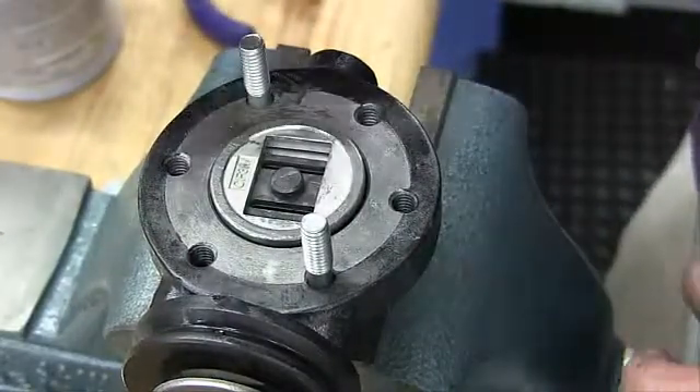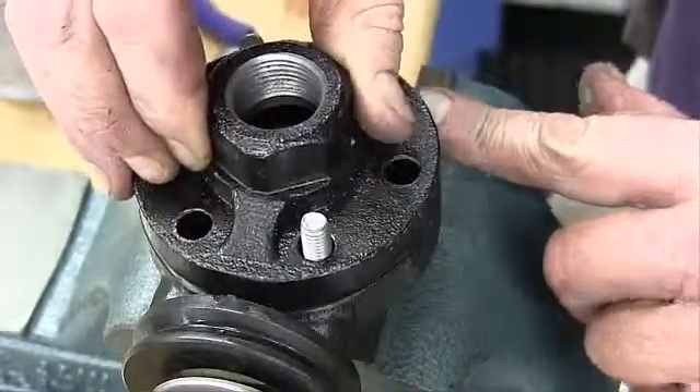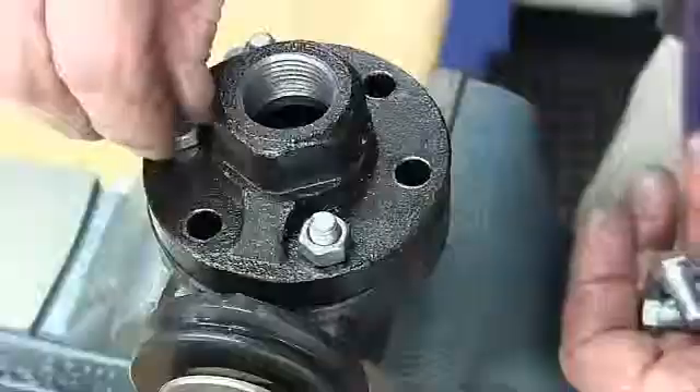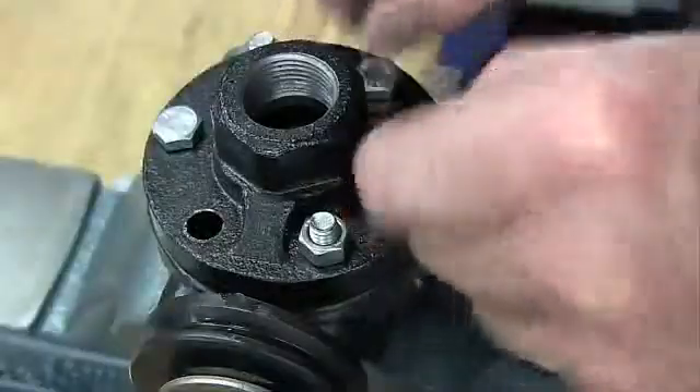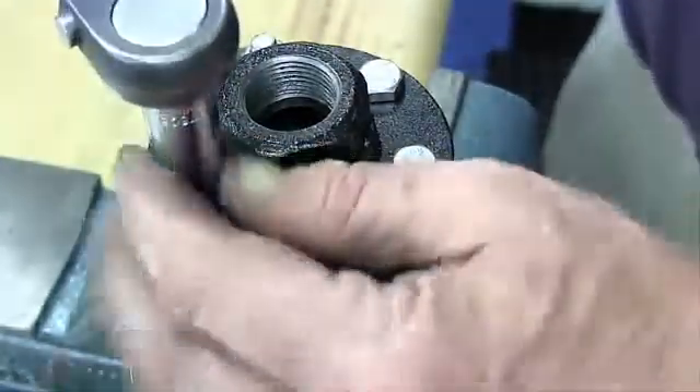Align the arrow on the cap with the arrow on the body, and place the cap over the two studs in the body. Install the nuts and cap screws and tighten uniformly. Now torque the nuts and cap screws. See the Mark 80 IOM for torque requirements and tightening procedures.